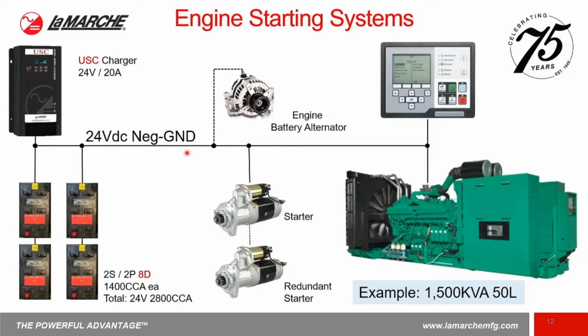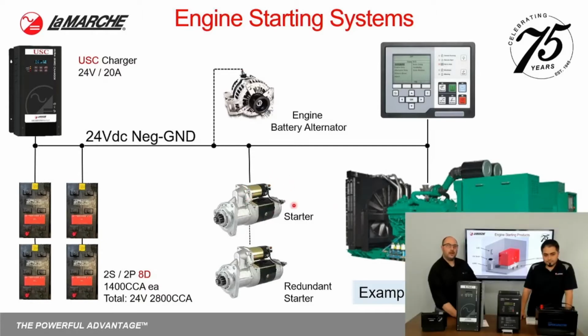So this DC bus, almost exclusively in the marketplace, this will be a negative ground system. In this size class of generator, you may have a redundant starter. This is kind of close to the borderline. Quite often there may or may not be an engine alternator for battery charging, and that would also be tied to the bus if it's there as well.